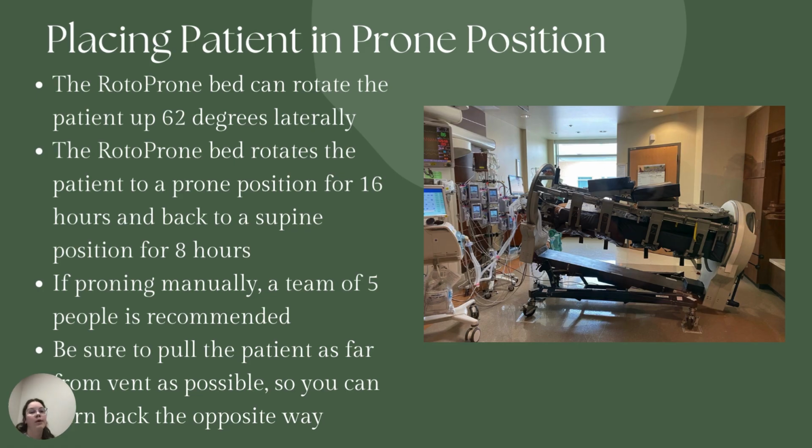And then we have placing the patient in the prone position. So this picture right here is a picture of a rotoprone bed. This can do what you can do manually to an extent. It can rotate the patient up to 62 degrees laterally, and this one is also in Trendelenburg. So it'll rotate them to a prone position for about 16 hours and then back to a supine position for about 8 hours. And it can keep doing that. That way you don't always have to have a team of 5 people to come in and help you.